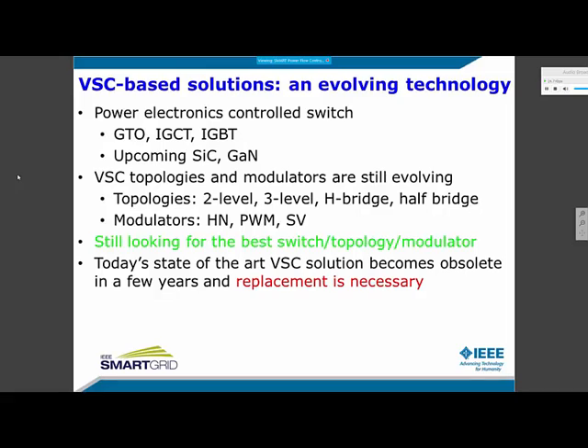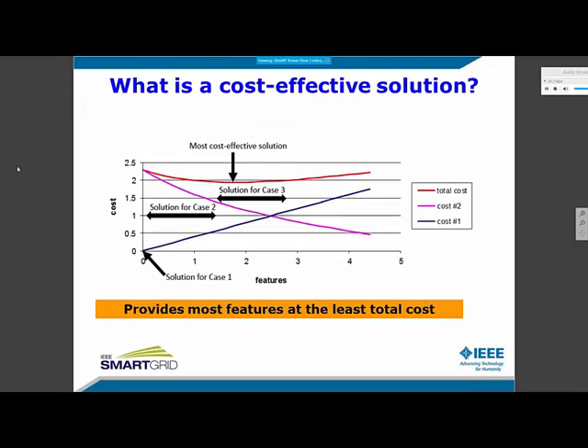Why? Let's talk about Westinghouse-made inverters. We built inverters with GTO thyristors. Now, when a switch fails, why not use the latest switch to replace the failed switch? Well, that's not possible because the gate drive, snubber circuit, and cooling requirements change from one switch to another. Therefore, it is necessary to replace the old inverter. And manufacturers would love to replace the inverters in a few years. But it won't be a good solution, a good return on the investment. So, an SVG solution for voltage regulation may not be perfect, but it's good enough.